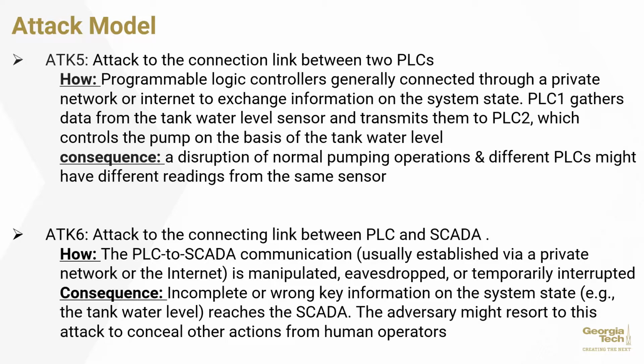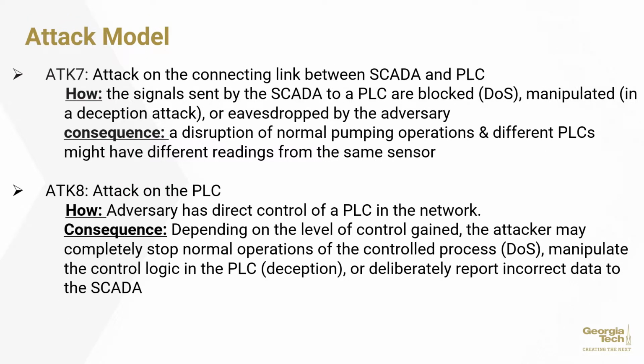On the other hand, attack number 6 is slightly different. It's an attack on the connecting link between a PLC and a SCADA. It typically happens by the PLC to SCADA communication being attacked, manipulated, eavesdropped, or temporarily interrupted. Consequently, it might cause incomplete or wrong key information on the system state to eventually reach the SCADA, and the adversary might resort to this attack to conceal other actions from human operators.